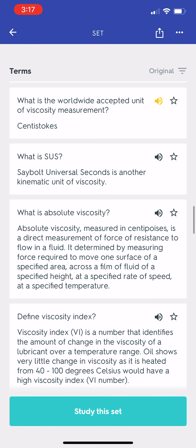What is the worldwide accepted unit of viscosity measurement? What is SUS? Saybolt Universal Seconds is another kinematic unit of viscosity. What is absolute viscosity? Absolute viscosity, measured in centipoises, is a direct measurement of force of resistance to flow in a fluid. It is determined by measuring the force required to move one surface of a specified area across a film of fluid of a specified height at a specified rate of speed at a specified temperature.